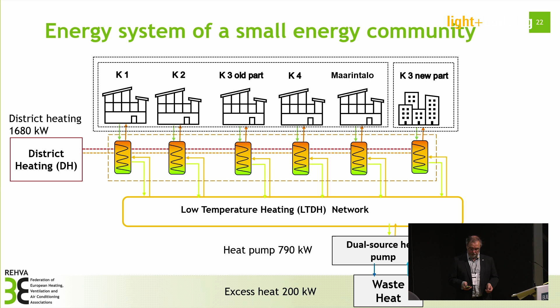Here we can also see the prices coming from electricity and district heating, and we are looking at which hours it is more profitable to use more district heating than heat pump. Now coming back, because we have varied energy prices, the whole thing becomes a little bit more complicated. With this dual energy source heat pump, the COP reduces quite significantly in cold weather: at minus 10 the COP is 2.5, and at plus 20 it is 3.3. So if the temperature is below minus 15, the outdoor air is not used for the heat pump because it doesn't make sense, as the COP is reduced quite a lot. And in the Helsinki climate, we have very cold periods from time to time. Our design temperature in Helsinki is minus 26.